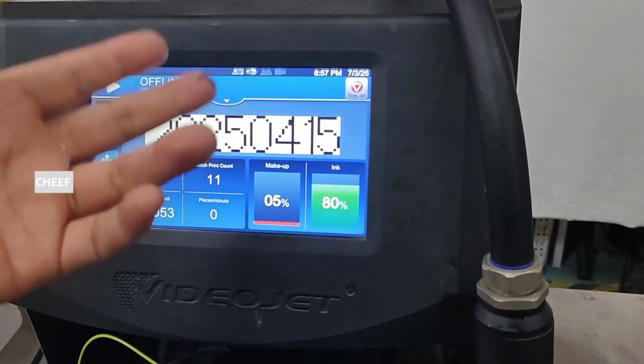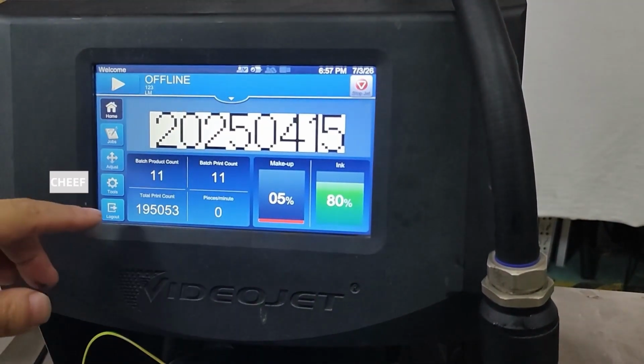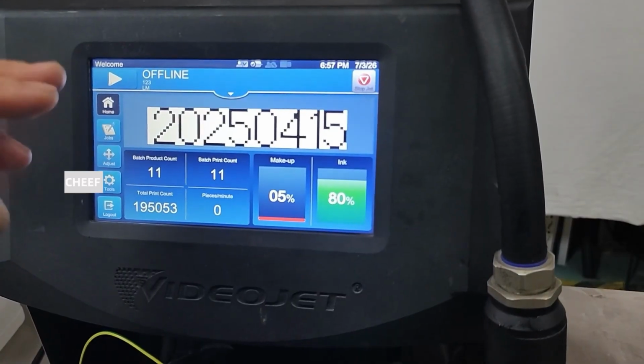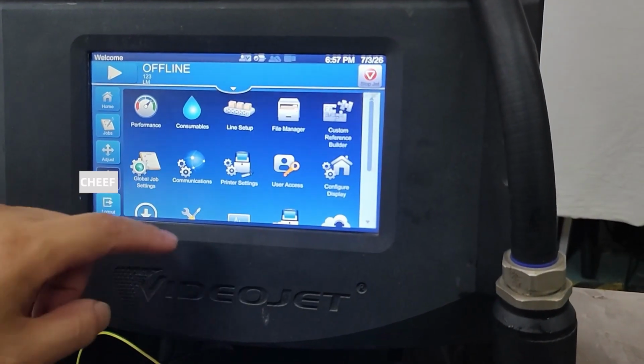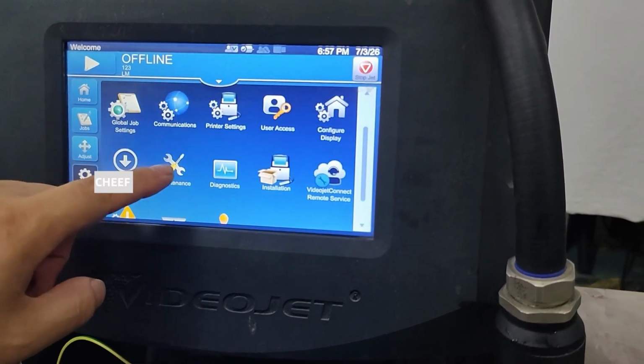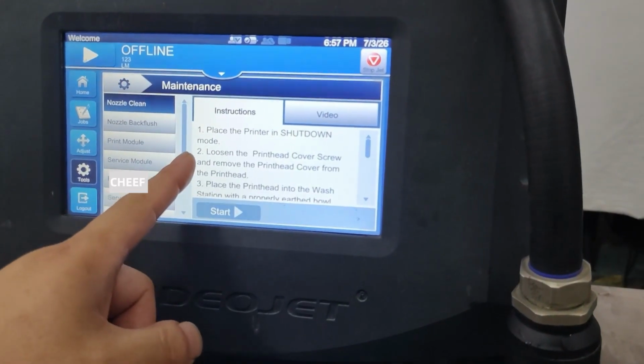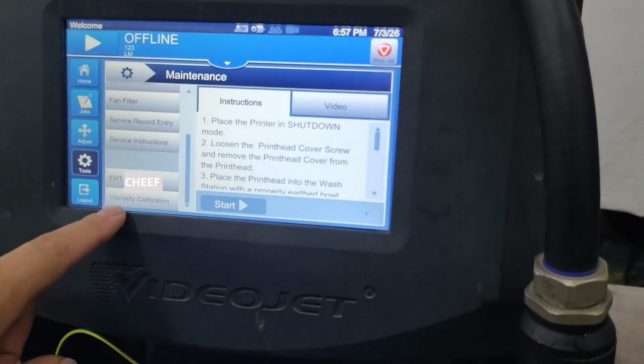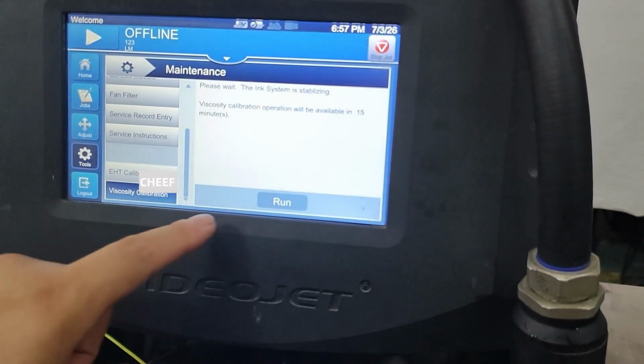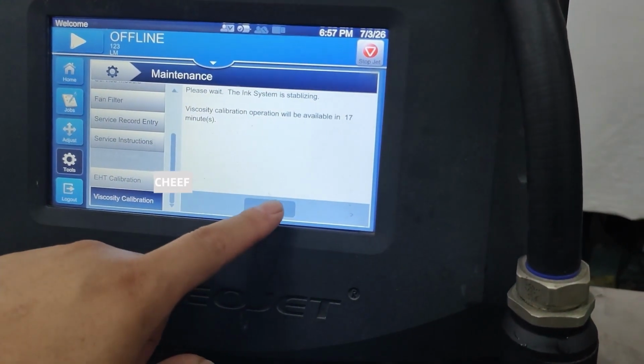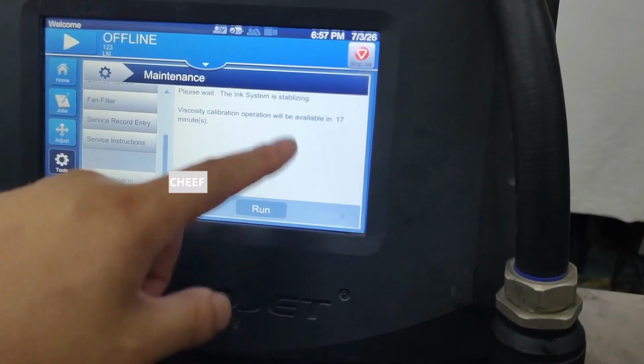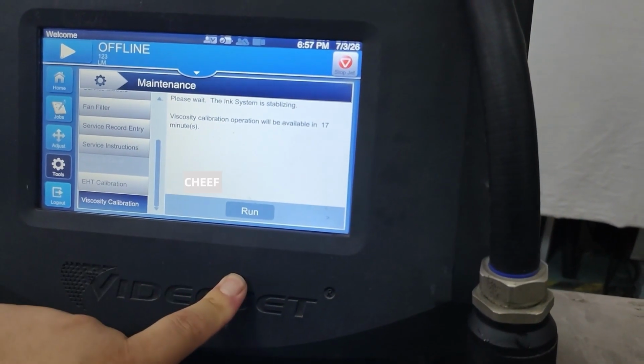But for a new machine, after it's just been started for about 20 minutes, we need to do an annual calibration. For annual calibration, go to Tools, Maintenance, and then select Viscosity Calibration. Just click it, and that's it. But right now, since I've already calibrated this unit before, it can't be calibrated again.